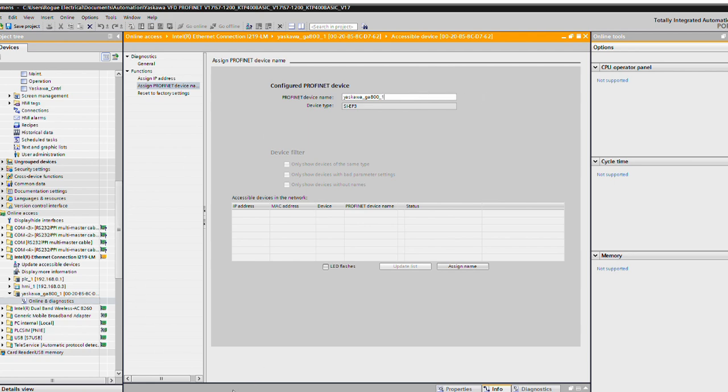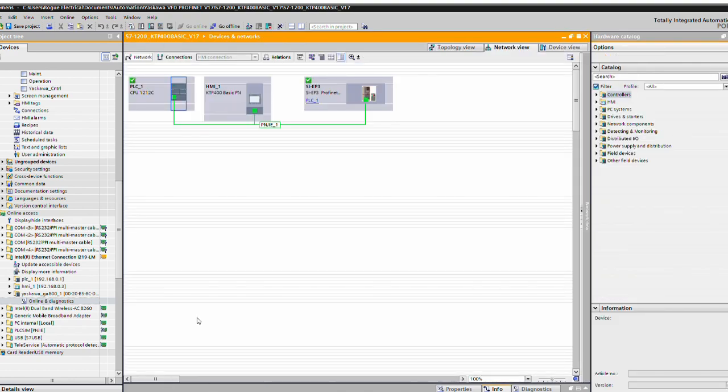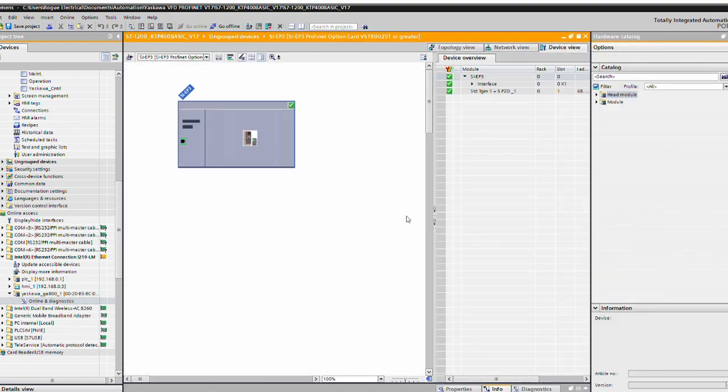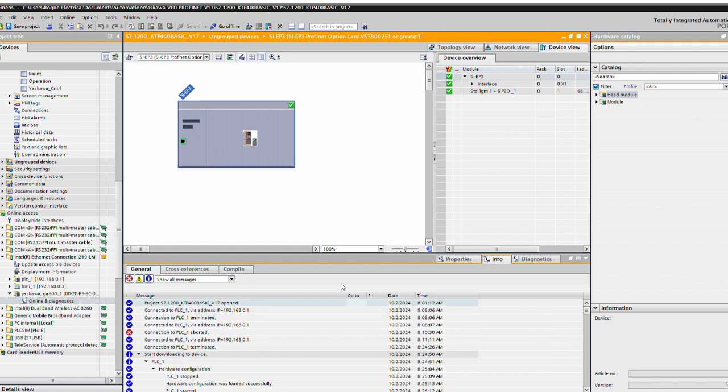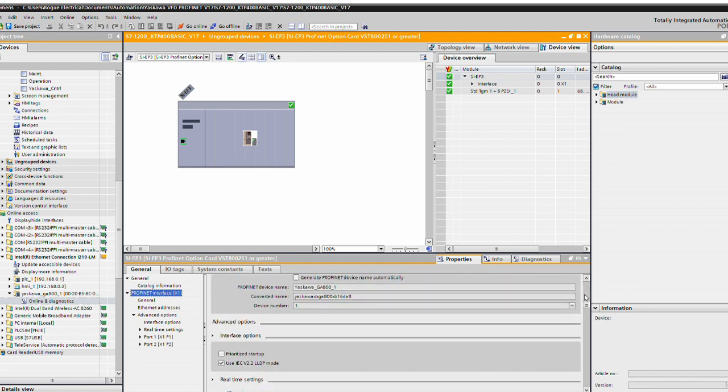So we're gonna go into the other tab over here. We're gonna look at our properties tab. Now that ProfiNet device name that you give it has to be the same as the one you assigned in this window for your ProfiNet device name. If you check generate ProfiNet device name automatically, just go ahead copy paste that and bring it into that window.